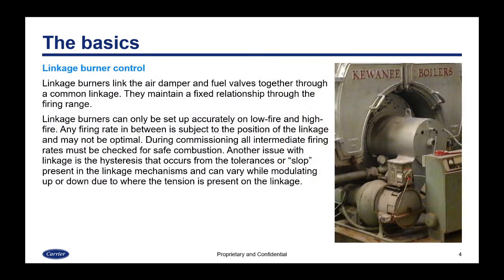With linkage burner control, the linkage will link the air damper and the fuel valves together through a common linkage, and because of that, they maintain a fixed relationship through the firing range. Linkage burners can only be set up accurately on either low fire and high fire, and any firing rate in between is going to be subject to the position of the linkage and may not be optimal. During commissioning, all the intermediate firing rates must be checked for safe combustion but can't be individually adjusted.